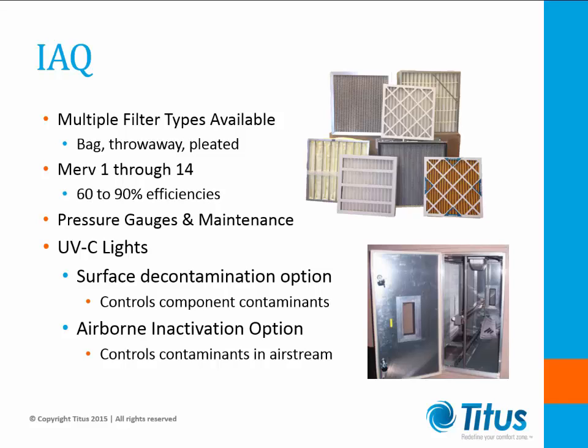UV lights are also used to clean surfaces within the air handling unit. The UV lights keep coils and drain pans clean of contaminants and reduces overall maintenance cost. These types of lights are typically referred to as surface decontamination. Using one or all the methods mentioned will keep coils clean, meaning less pressure drop and lower fan power requirements.